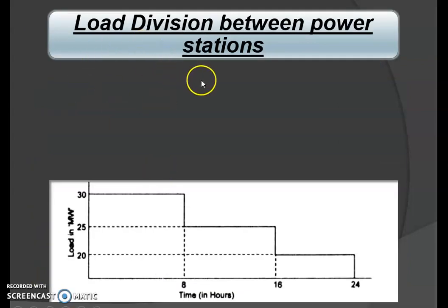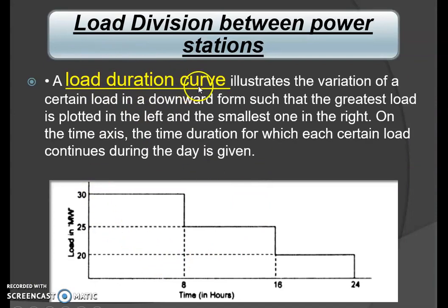So this is the load division between the different power stations. So this is the load division chart. A load duration curve illustrates the variation of the load in a downward form such that the greatest load is plotted on the left and the smallest one on the right on the time axis. The time duration for which each certain load continues during the day is given. In this load duration curve, it is drawn for 24 hours of the day. On the y-axis there is load in megawatt and on the x-axis there is time in hours. The maximum load, let us suppose here it is 30 megawatt, is plotted first, then the next lowest, then the next lowest, and so on. The 24 hours are covered for a day.